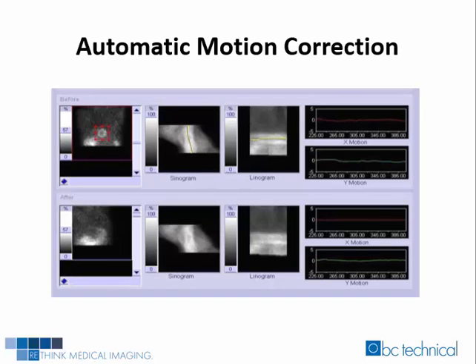Automatic motion correction was performed on a Siemens e.soft workstation. The manual states to place the red box around the heart without touching the organ. Once the red box is around the heart, go to the linogram and sinogram images and compare the results. The horizontal line on the series frame indicates the row of pixels used to create the sinogram. The same row of pixels from each frame is extracted and stacked from top to bottom to create the image. All edges of the sinogram should be smooth; a rough or displaced edge may indicate patient motion. To make a linogram, each frame from the raw data is summed into a column. The first image is placed on the left and the last image is on the right, so you read the linogram left to right. All edges on a linogram should be smooth, and any rough or displaced edge may indicate patient motion.